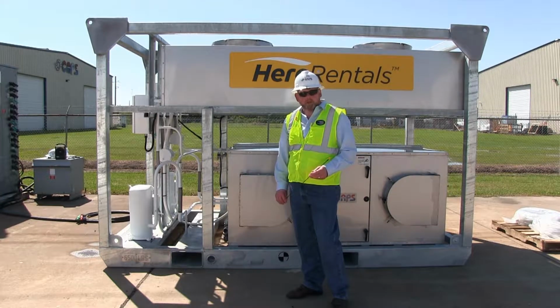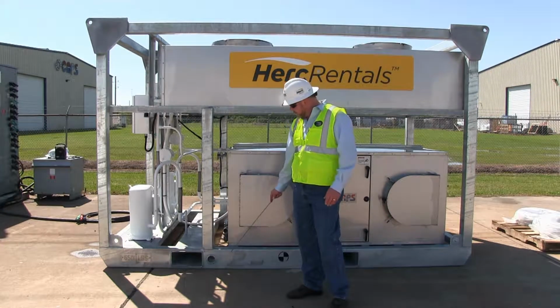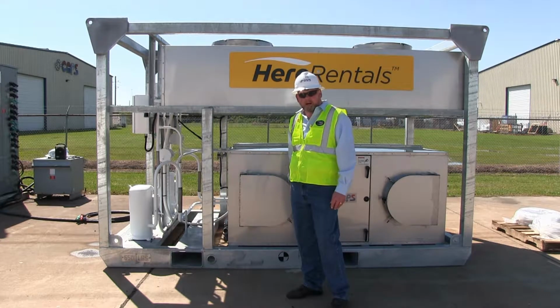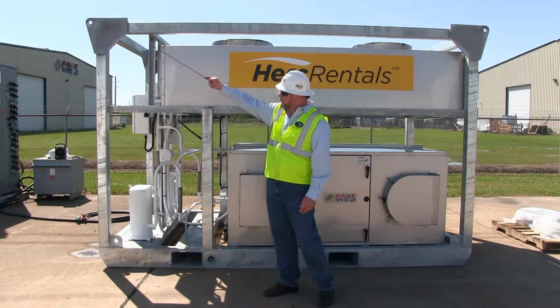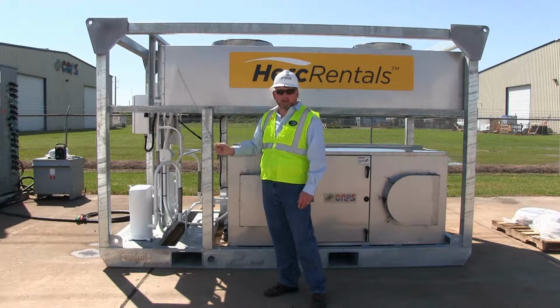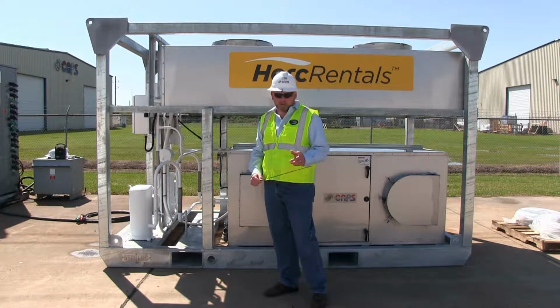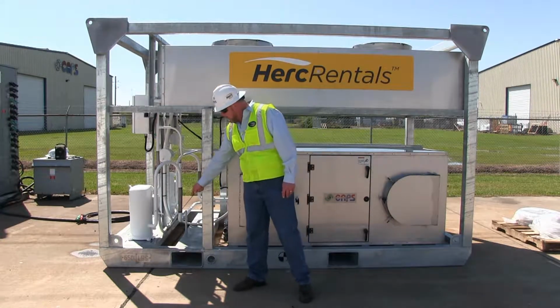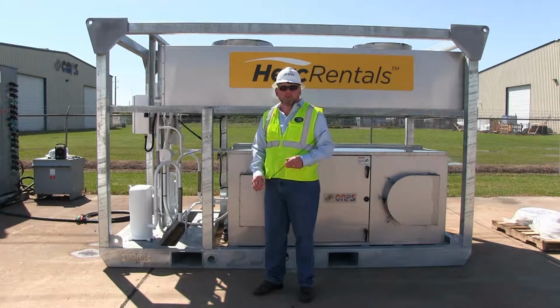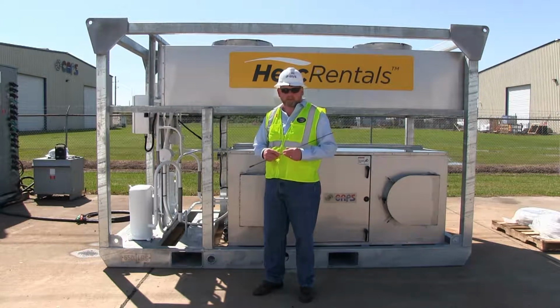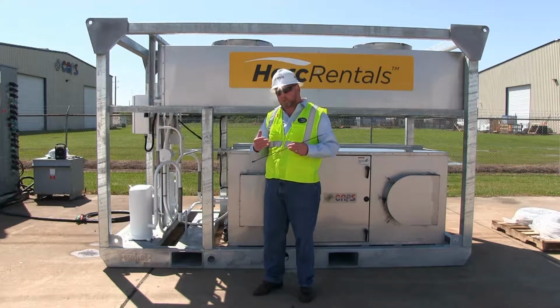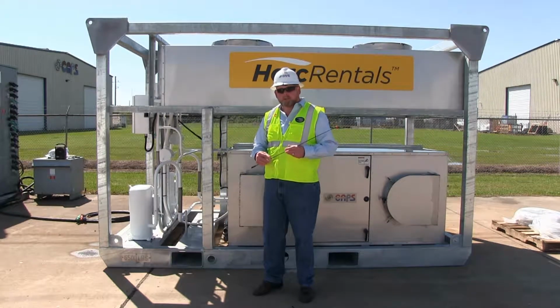The 40-ton unit is designed to be transported by two different methods. One is with the forklift pockets located at the bottom, or overhead lifting shackles at the top to allow for single point lifting. It's very important that you check the bottom weight tag on every unit to ensure that the operator of the forklift has the correct size unit or the crane operator. Each unit needs to be set on a stable level ground.